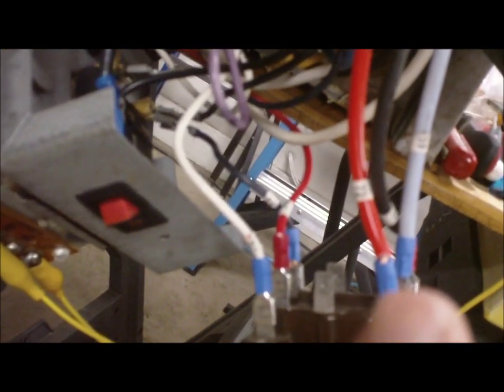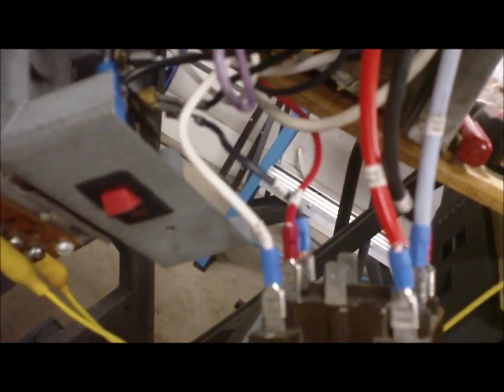The fan switch, the fan limit switch, is connected to this yellow wire right here, 120 volts, and also the low speed and the high speed of the blower motor are connected to this relay. For this one, like I said before, one is connected for your limit switch, and one for your pressure switch. And behind it are these two wires right here. You can see.